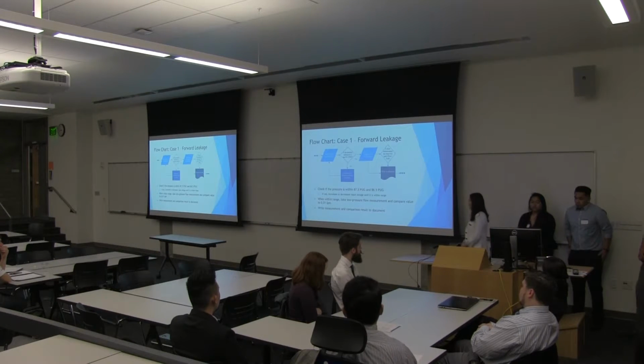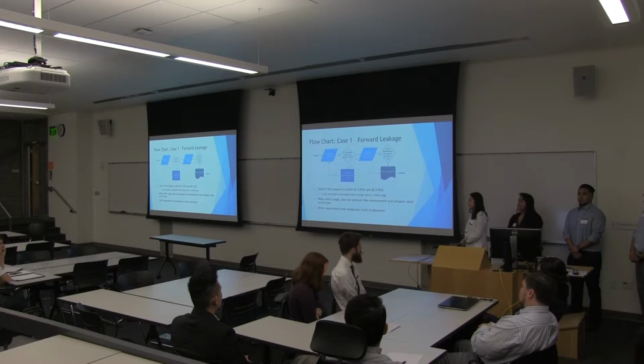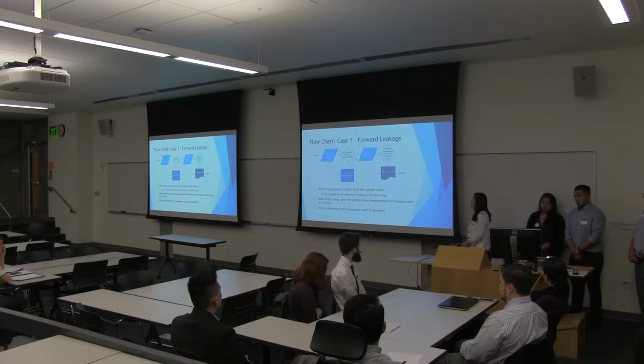Once it is within range, we'll take the low pressure flow measurement and write that to the document, as well as compare it to see if it is less than 0.01 liters per minute. That is also written to the document. If it passes, it will be written as pass. If it fails, fails.